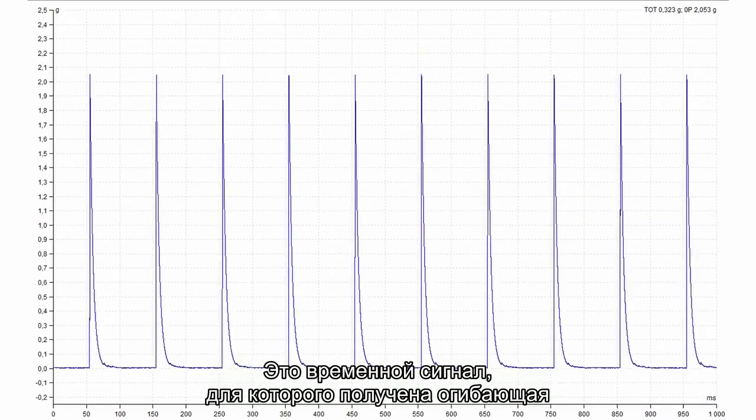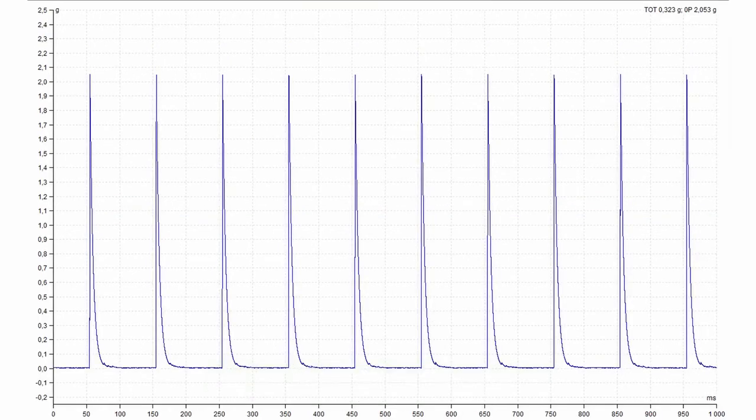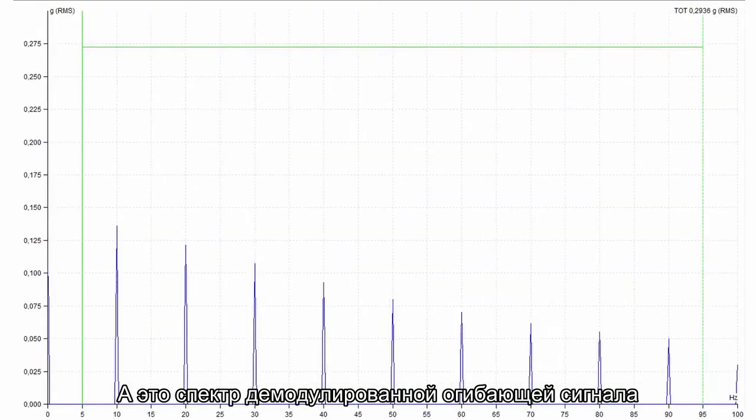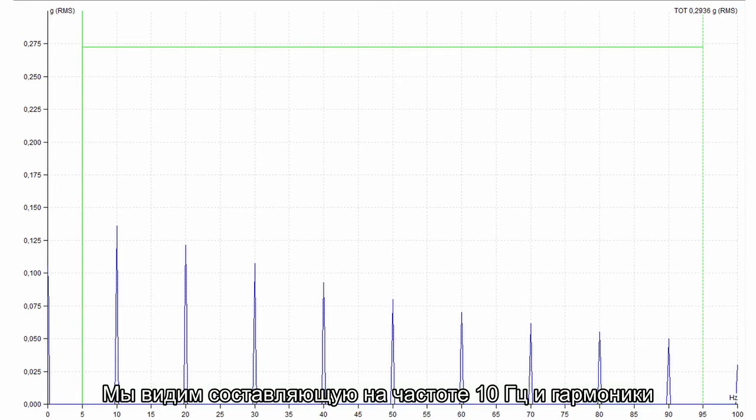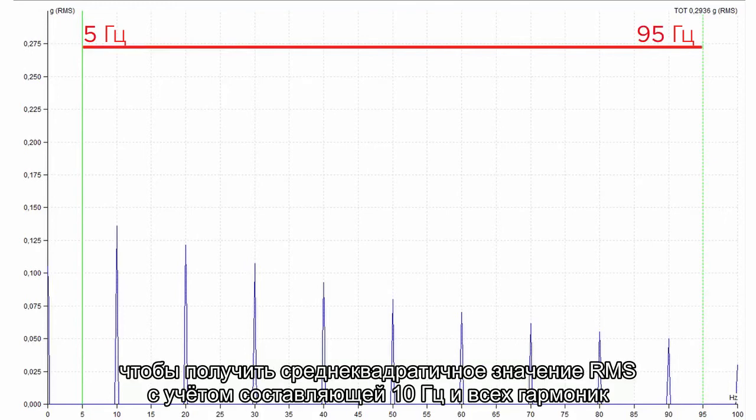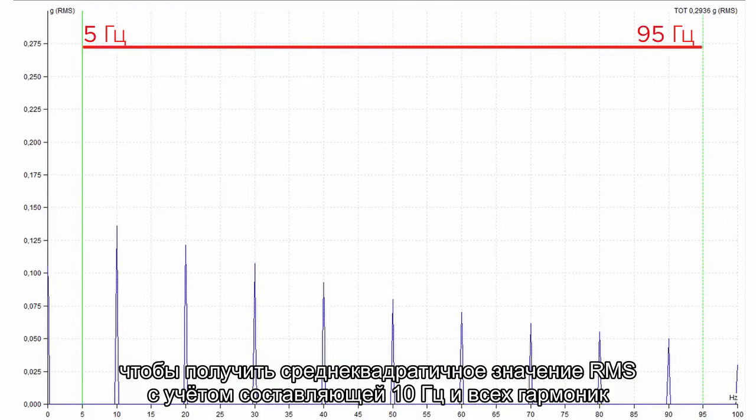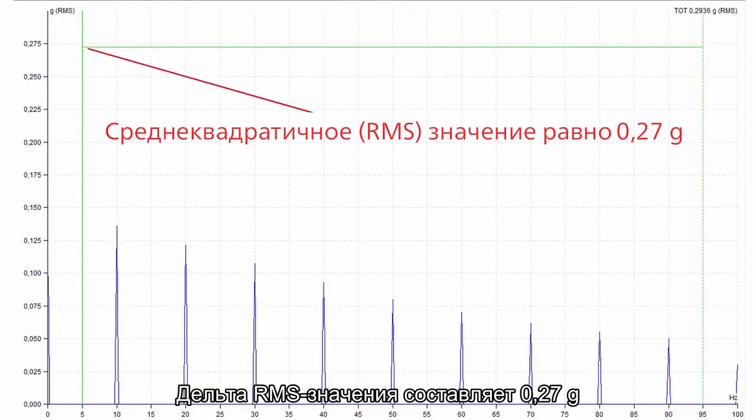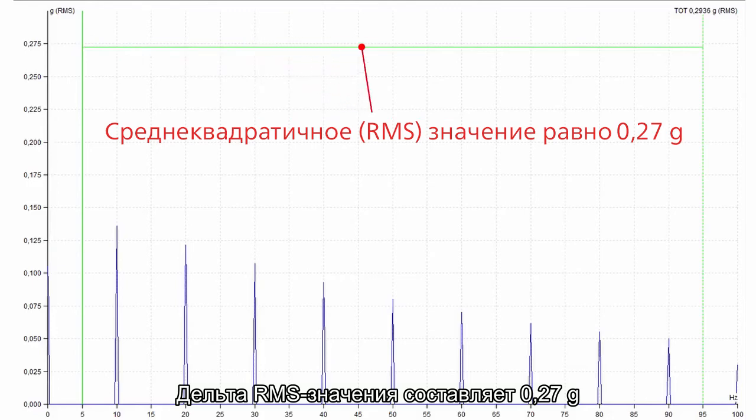This is the time signal after enveloping. And this is the demodulation spectrum made from that signal. We can see the 10 Hz amplitude and the harmonics. I define the delta cursor from 5 to 95 Hz to get the RMS sum of 10 Hz and all harmonics. This delta RMS value is 0.27 G.